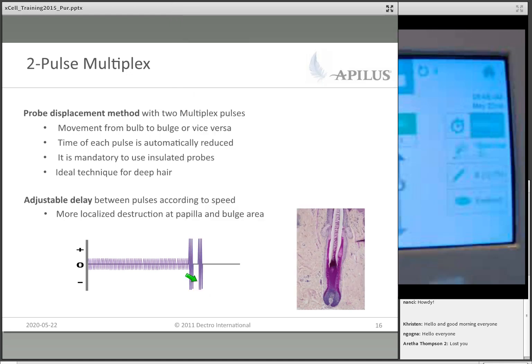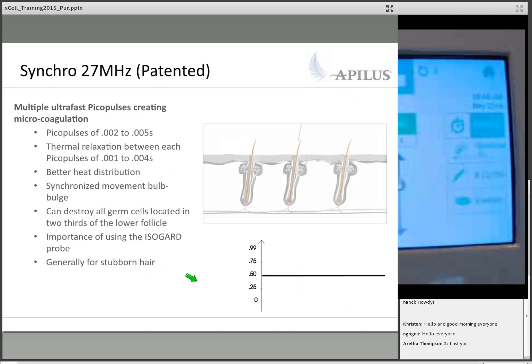So when you press on the foot pedal and it goes the 6 beeps, you have a different tone at the very end. So sometimes when you get used to this, you should go through a pulse, make sure that you understand the different tonalities so that you know when to lift your foot off, especially when we go through the blends. This just shows the pre-warming there. We're back on our PowerPoint. And then the first pulse moving up because we're doing displacement and doing the second pulse at the bulge area.